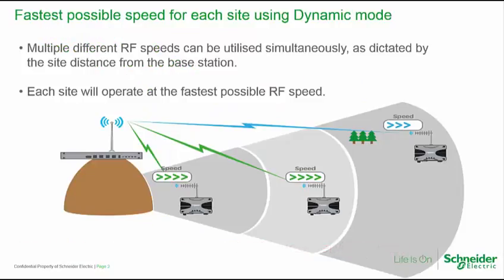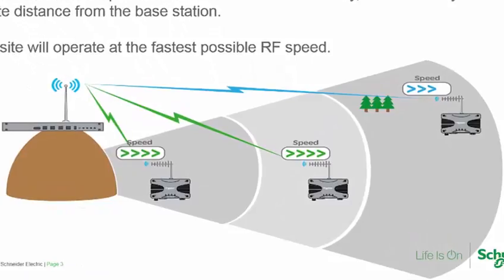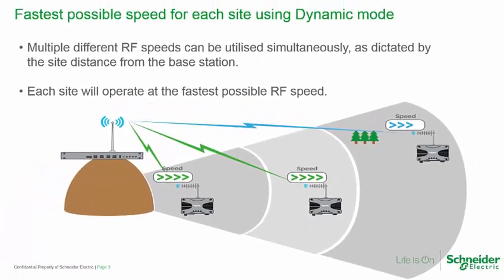With each radio able to adjust its speed dynamically, the system can typically operate more quickly in normal operation. Even though the faster speeds may not provide a 20 dB fade margin, the system remains reliable because each radio will automatically reduce its speed whenever necessary to maintain reliability. Some remotes may need to typically operate at slower speeds, as they are at a greater distance or the path may be more heavily obstructed. At the same time, other sites will operate at faster data rates, as dictated by their own conditions.